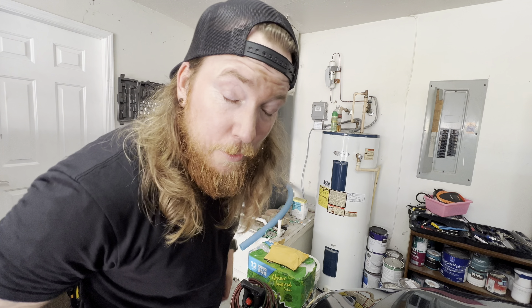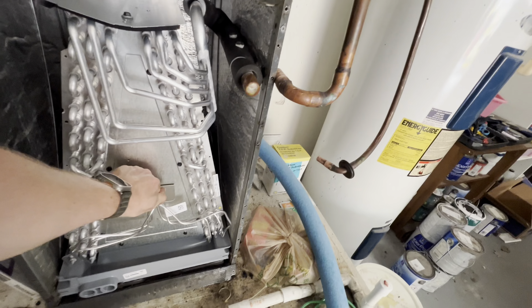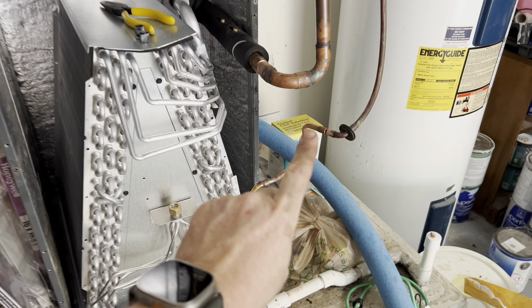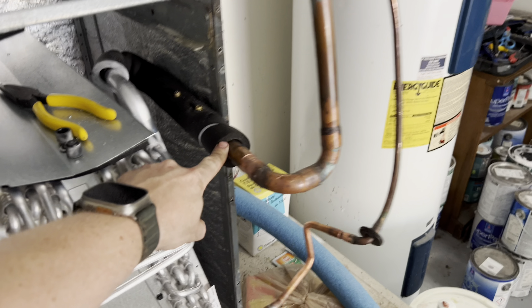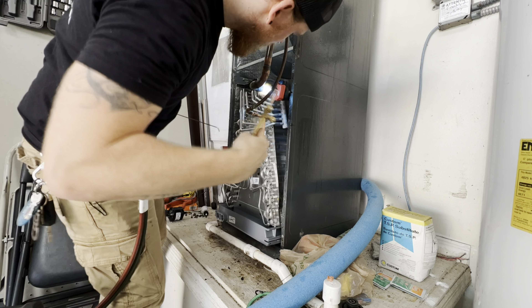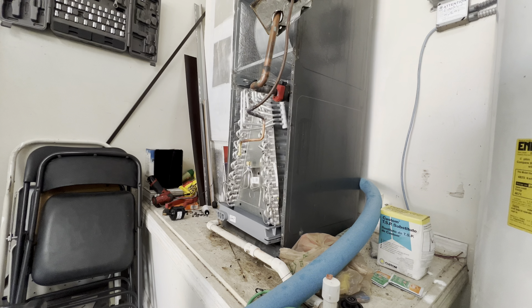I ain't recording because I'm annoyed. I got to go back to Goodman and get a part for this. That's why I hate Goodman. So I flushed it, I'm just going to keep it as is, going to braze this all up, put a little rag here. I'm going to run over to Goodman and get a new TXV, because with all that oil I don't even want to bother with this one. I'm going to run out, do that, after I braze this.